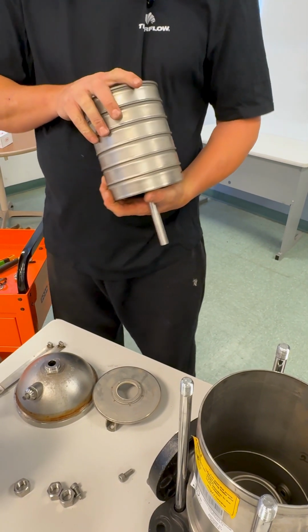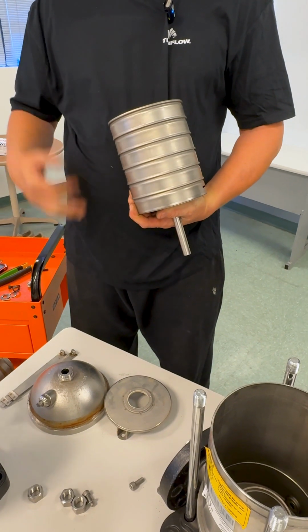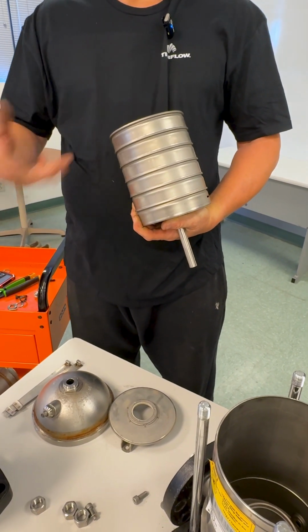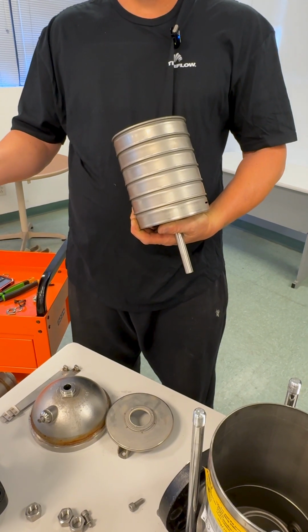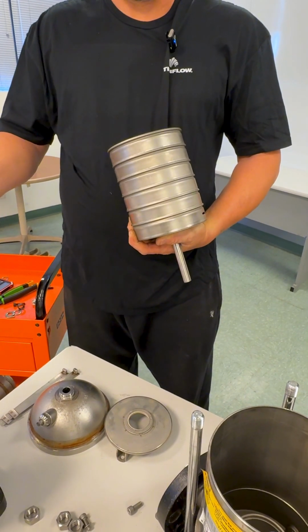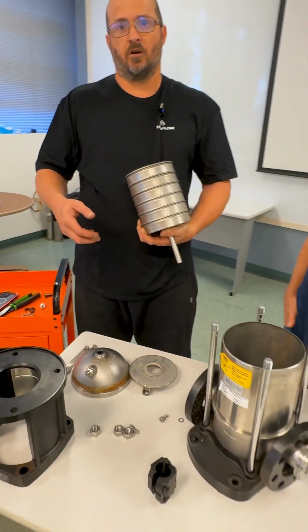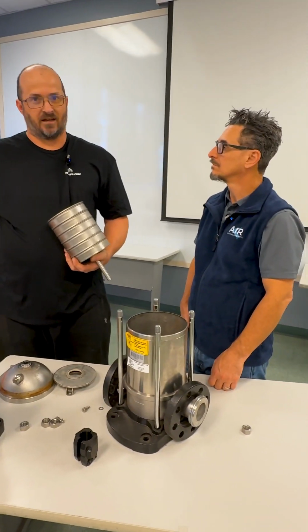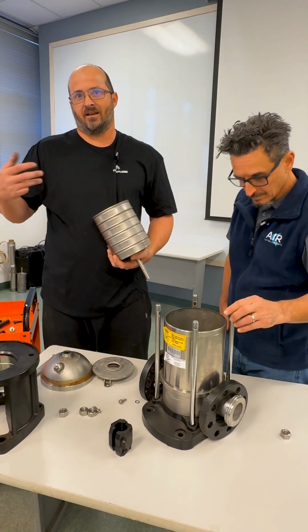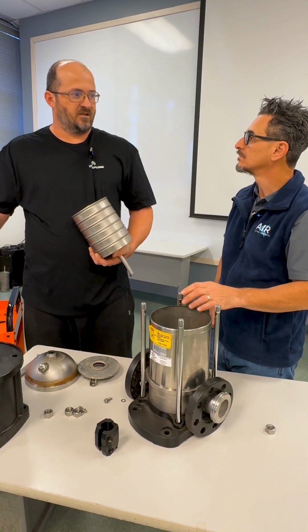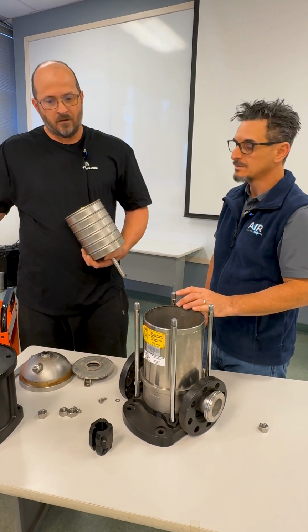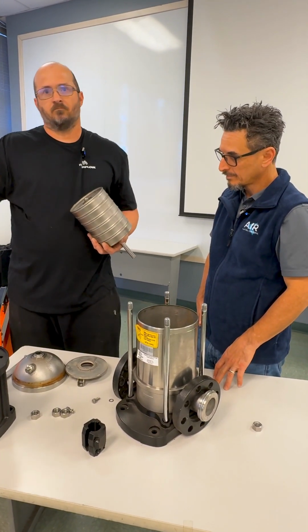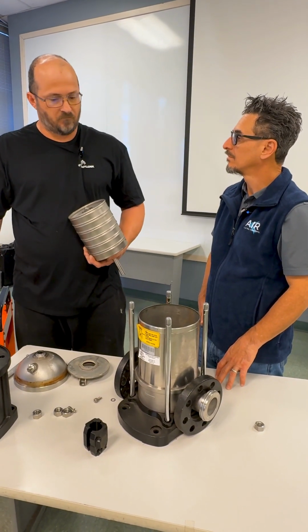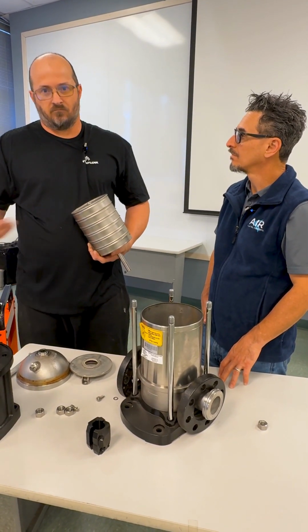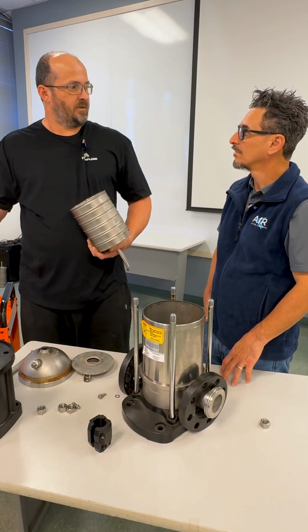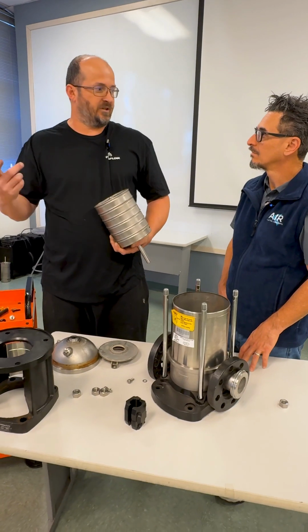Typically this would operate off of a VFD, coming on based on pressure. Say they wanted 100 PSI—at 92 or 90 PSI the pumps would kick on and ramp up until they hit 100 PSI. If one pump couldn't maintain it, a second pump would come on to assist until it maintained 100 PSI. With the VFD, it ramps up and down doing its thing. Once satisfied, one pump shuts off and the other takes over, maintaining it by itself.